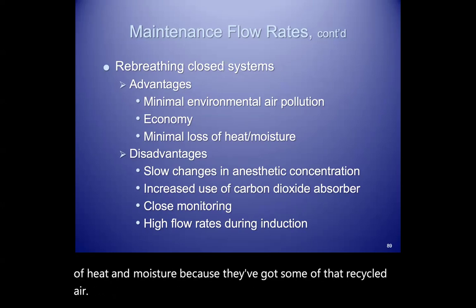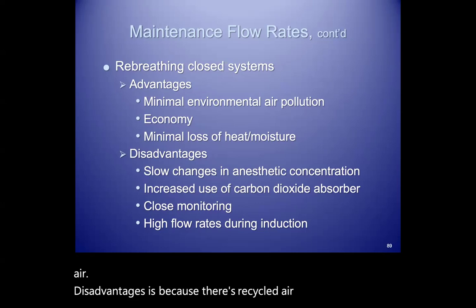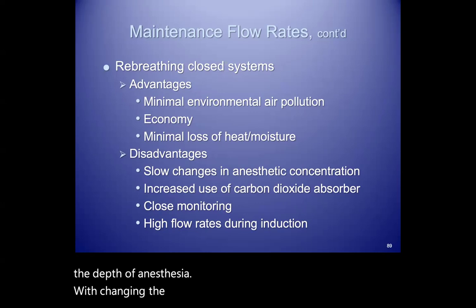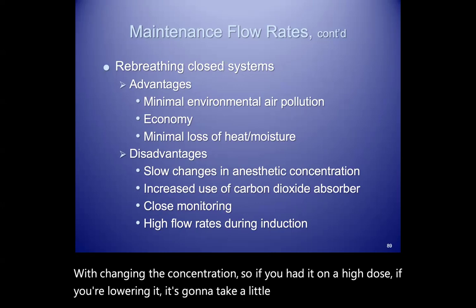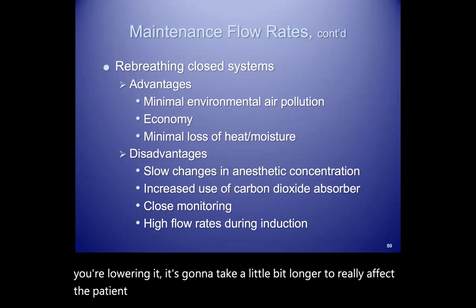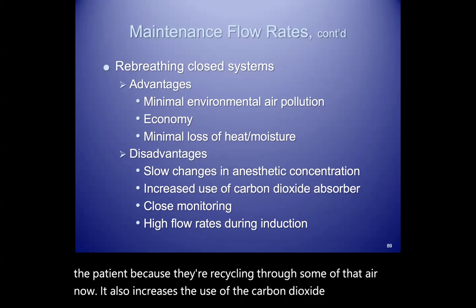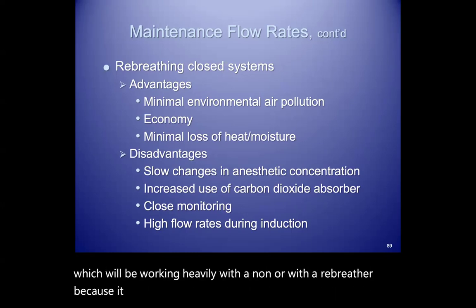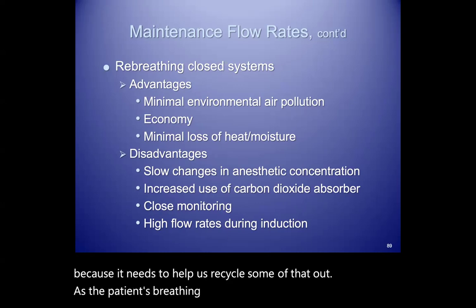Disadvantages is because there's recycled air, it's harder to control the depth of anesthesia with changing the concentration. So like if you had it on a high dose, if you're lowering it, it's going to take a little bit longer to really affect the patient because they're recycling through some of that air. Now, it also increases the use of the carbon dioxide absorber, which will be working heavily with a rebreather because it needs to help recycle some of that out as the patient's breathing in. And again, they are on full flow oxygen as well.